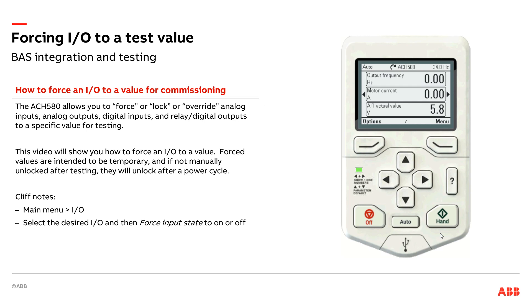I'm going to use the word 'force' because that's the terminology in the drive. However, based on your controls background, you may choose to use the word 'lock' or think of this as an override. So I'm going to force, lock, or override my inputs — whether that's an analog input, analog output, digital input, or relay outputs. I can force all those things to a specific status, whether that's high, low, open, closed, or a voltage. So let's take a look at how to do that.